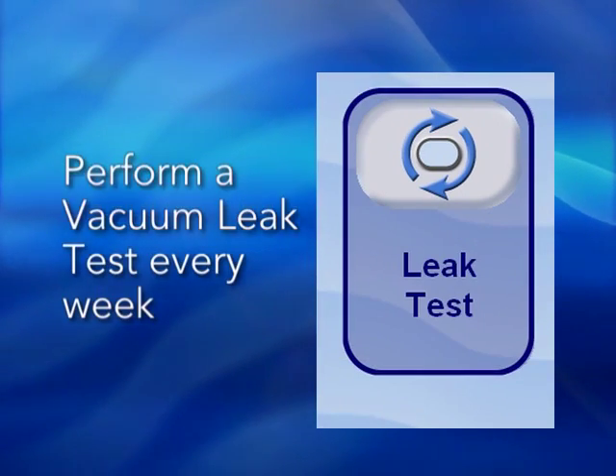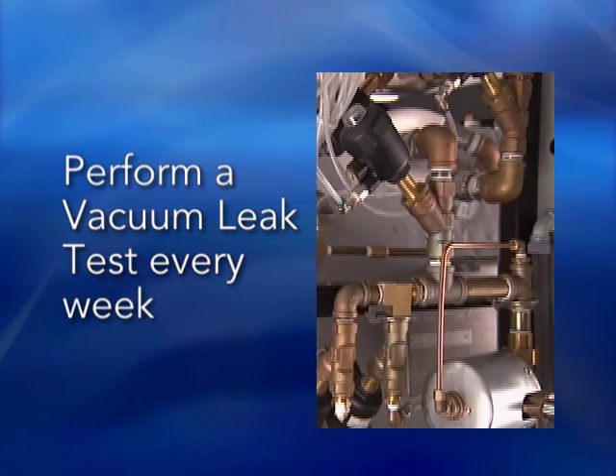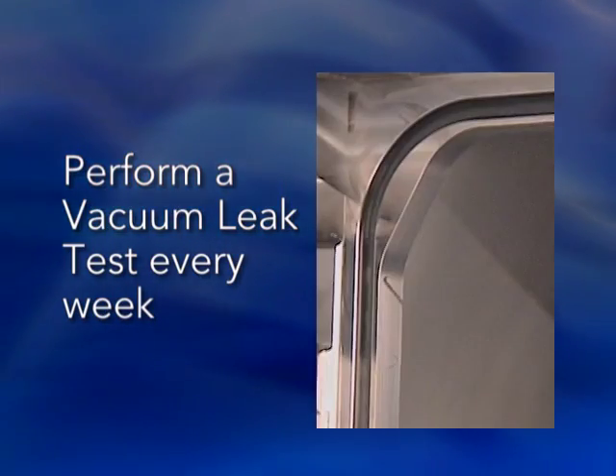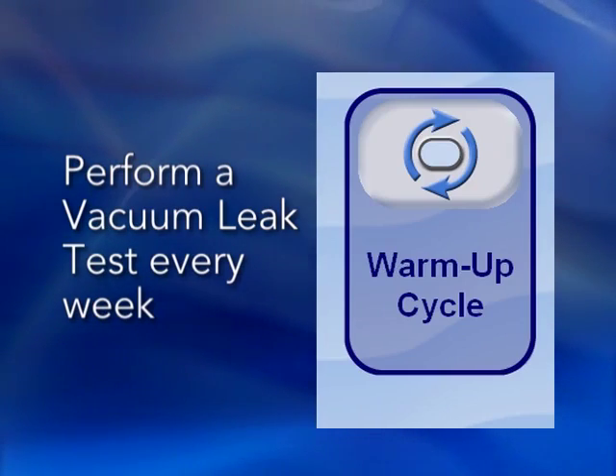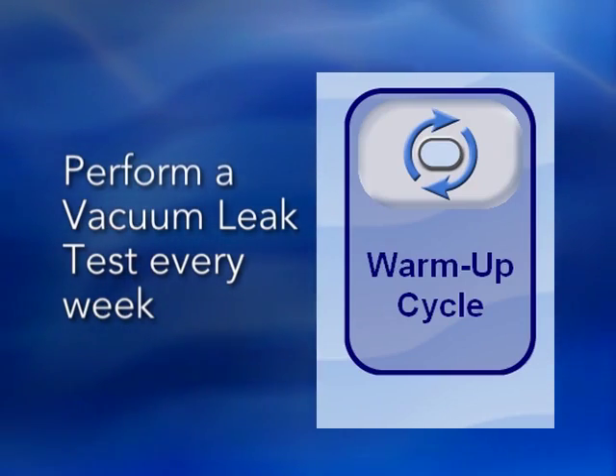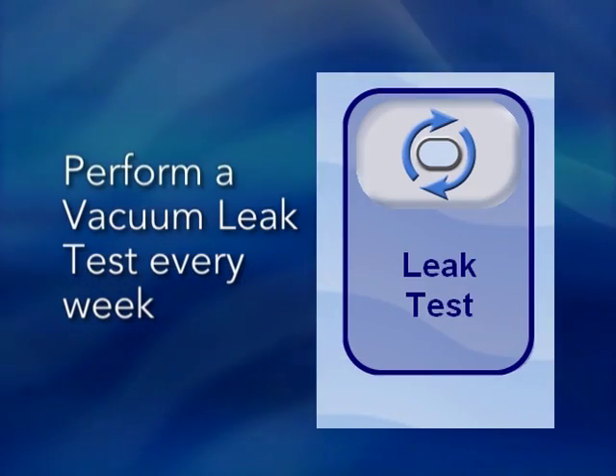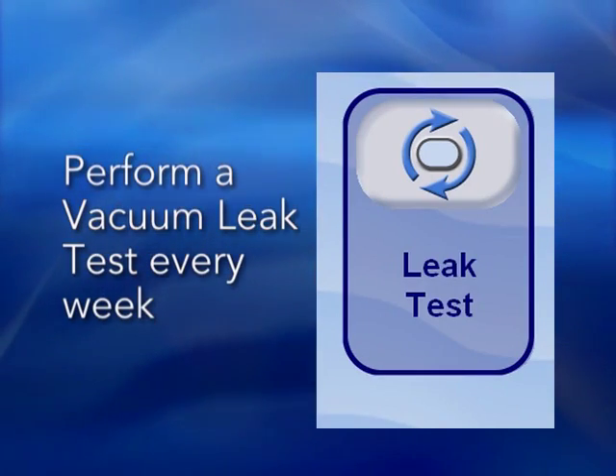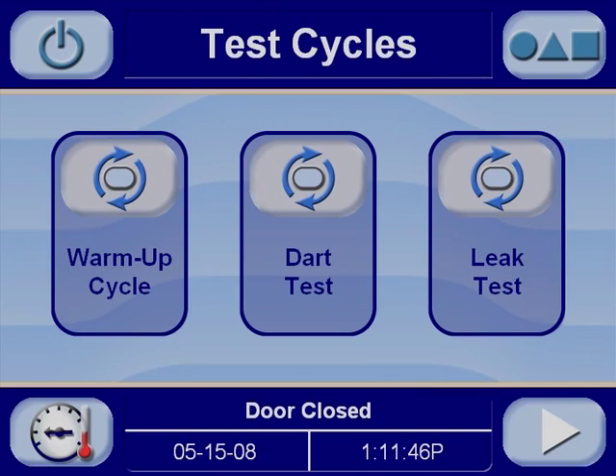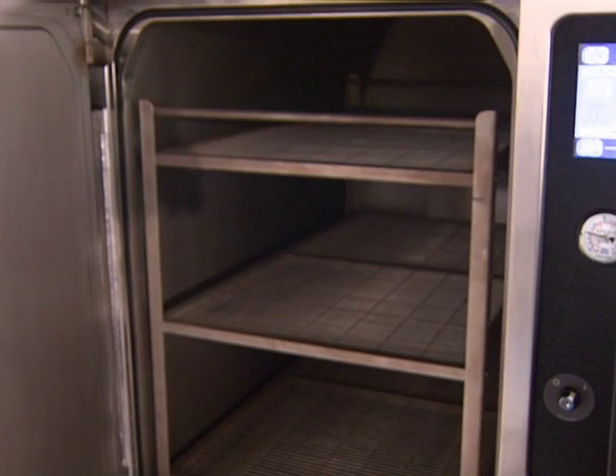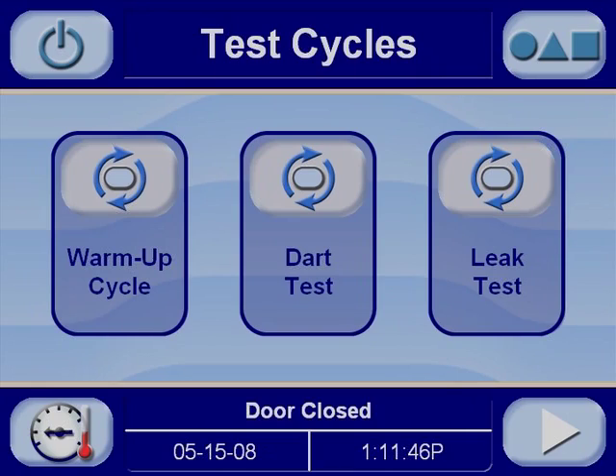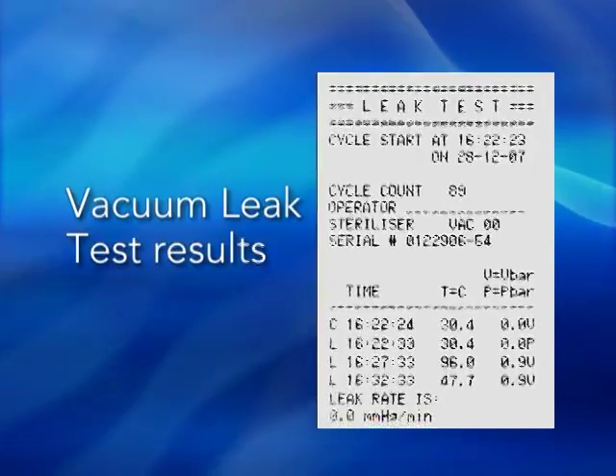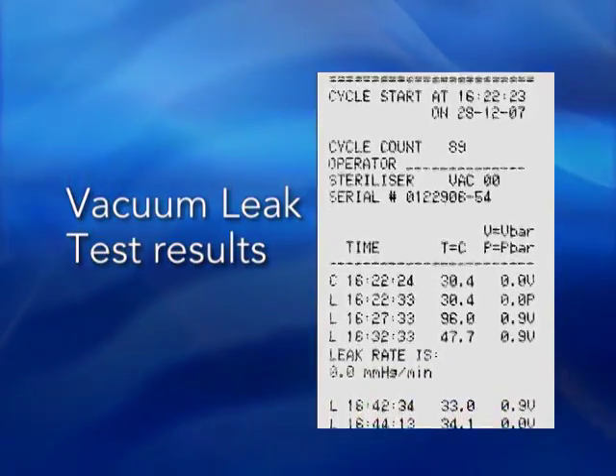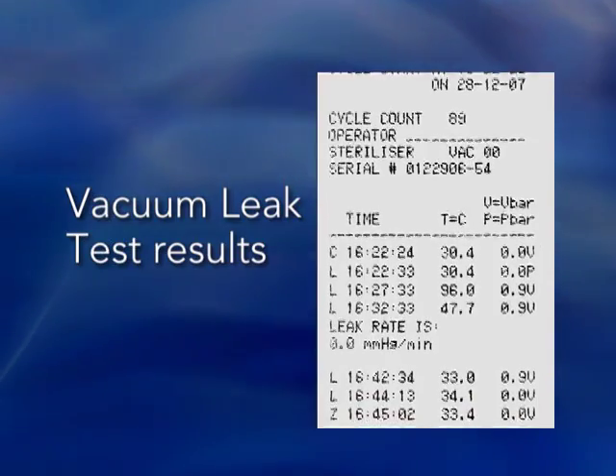The vacuum leak test should be performed at least once a week. It automatically checks for leaks in the piping and door seal. To ensure valid test results, always run a warm-up cycle before performing this test. When the warm-up cycle is finished, initiate the vacuum leak test. From the Test Cycles menu, press the Leak Test button. The sterilizer chamber must be empty while running the test cycle. Again, the vacuum leak test cycle values are pre-programmed and cannot be adjusted. The entire vacuum leak test cycle is also documented on the printout and includes a leak rate value.